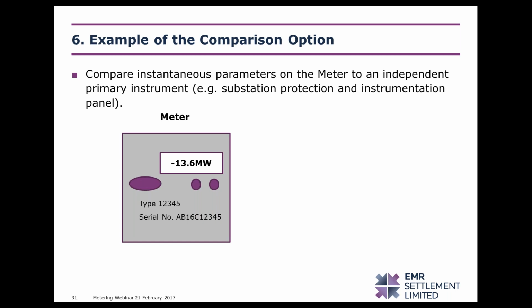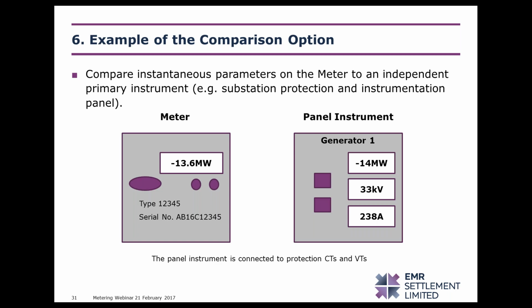One of the techniques that can be used is to take a photograph of the meter, clearly showing the serial number of the meter so it can be identified as the CMU meter, showing the display of the meter with a prevailing load on it. In this case, it is showing a prevailing primary energy value showing an active export of 13.6 megawatts. At approximately the same time, you will need to take a photograph of the independent measuring instrument. In this example, in another part of the substation, there is an instrumentation panel that is connected to protection CTs and VTs that is showing a value of export of 14 megawatts.